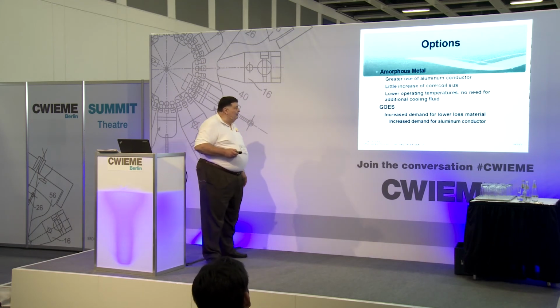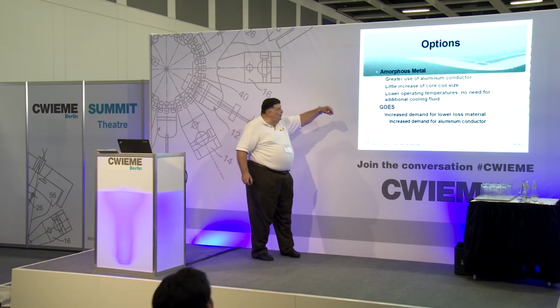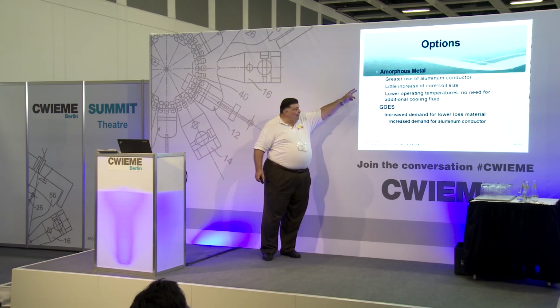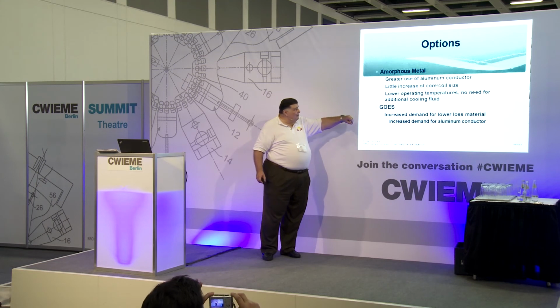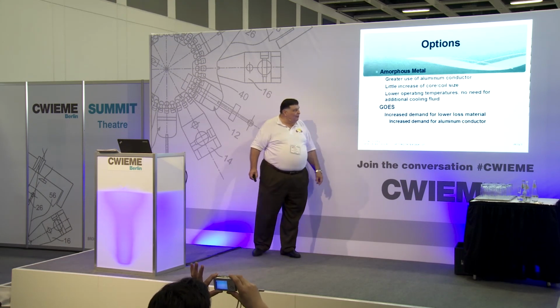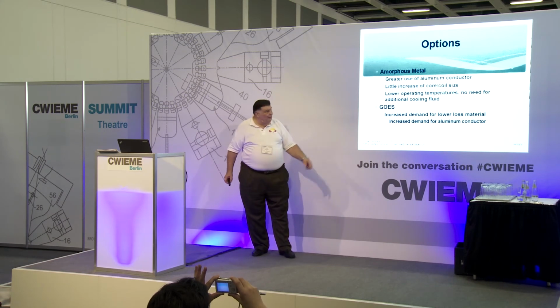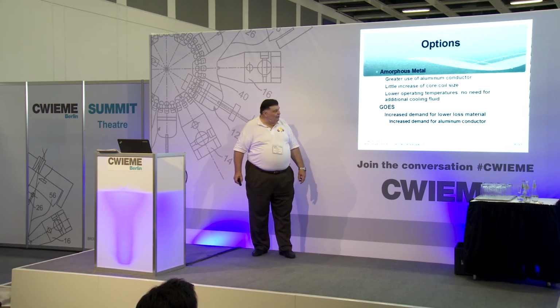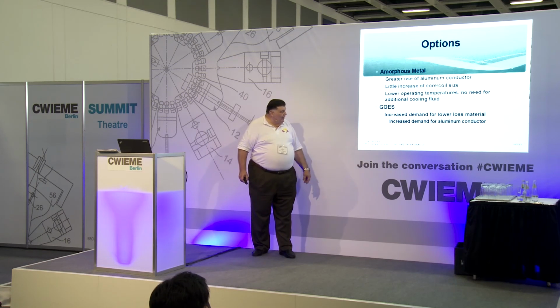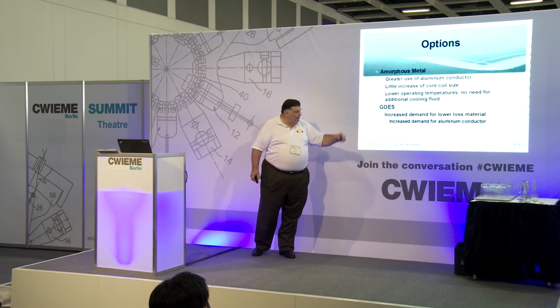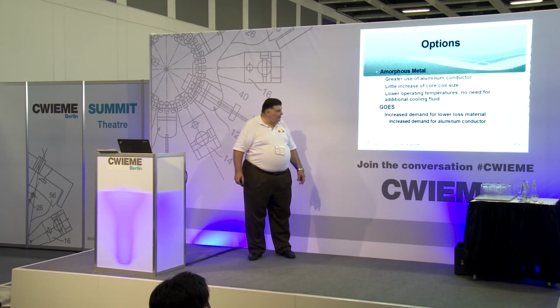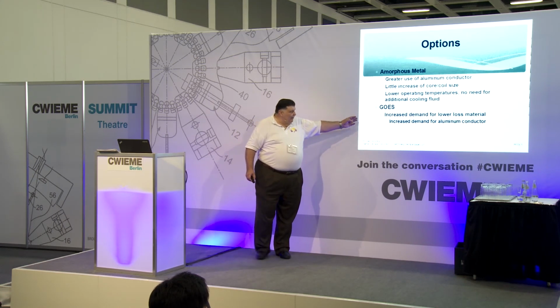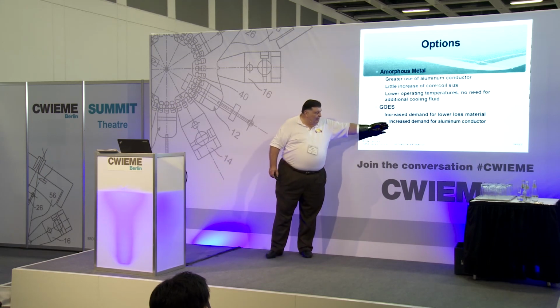What are the options? Greater use of amorphous metal, and with it comes greater use of aluminum conductor. Using amorphous, there's a little increase in core size or coil size, lower operating temperatures, and no need for additional cooling fluid. With grain-oriented, it's an increased demand for the lower loss material, and if that can be achieved, then an increased demand for aluminum conductors.